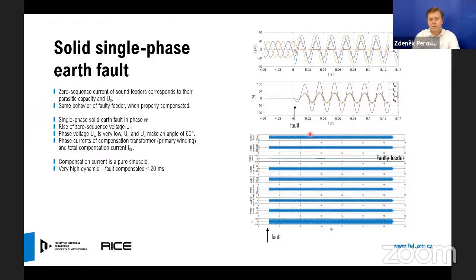Just a few waveforms. These are recordings from a solid single-phase earth fault. Here you see the phase-to-ground voltages. This is the moment when the earth fault occurs. You can clearly see how the zero sequence voltage increases. This is the magenta line. And here you can see how our device immediately reacts, increasing the compensation current. The magenta one is the total compensation current, and the remaining waveforms represent the phase currents at the primary winding of the compensation transformer.